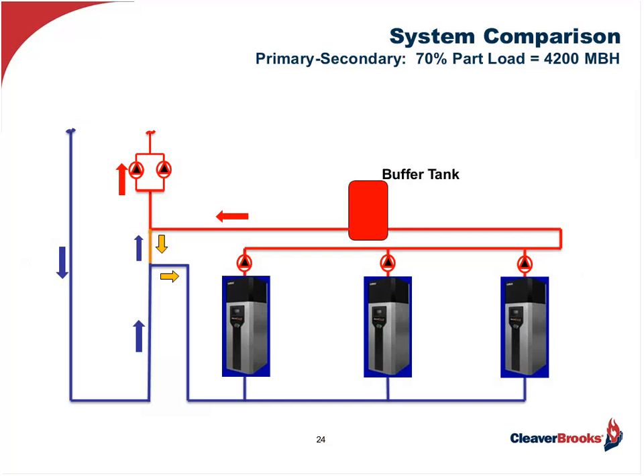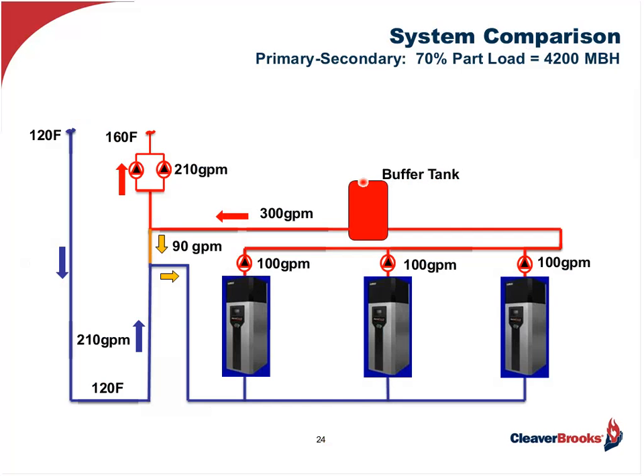Now what happens at part load? Let's look at 70%. Again, 160 out, 120 coming back. We're going to assume no outdoor air reset at this point. That gives us a flow rate of 210 GPM. Now, because we want to have a primary rate greater than the secondary rate so we get the right kind of mixing, we're going to have all 3 boilers running at 100 GPM. That gives us 300 GPM in the primary loop. What does that do for us? Well, now we have 90 GPM coming back through that decoupler.